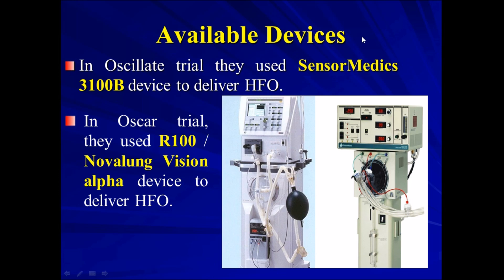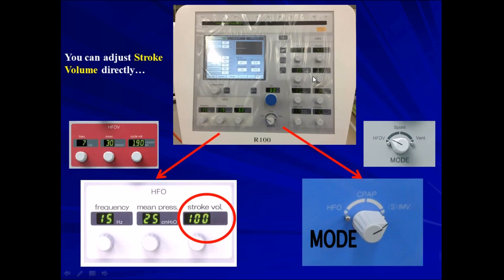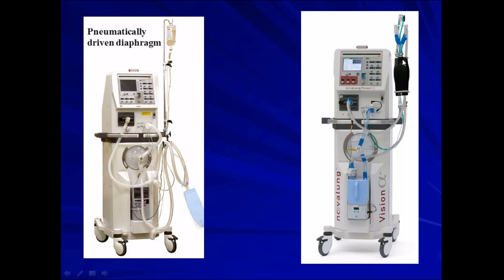Available devices in real life: there are two main devices. One is the SensorMedics 3100B, which was used in the Oscillate trial. The other trial, the OSCAR trial — the English trial — used the Japanese device, the R100, also known as the Novalung Vision Alpha. This second device is slightly different: it has high frequency built in plus conventional mechanical ventilation, so you can shift the patient directly on the same device. It does not control delta pressure; it controls tidal volume or stroke volume directly. The comparison between these two devices is beyond the scope of this presentation.